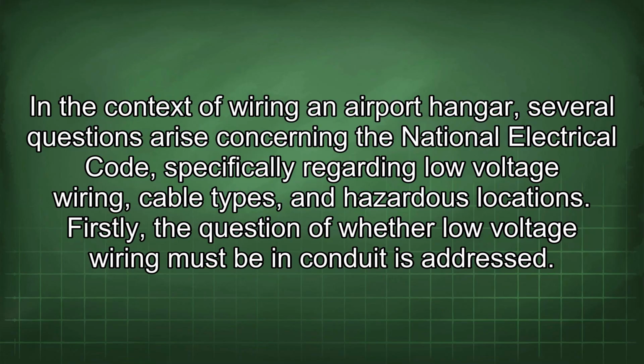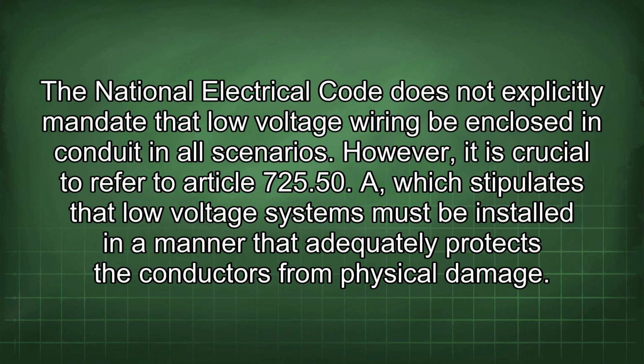In the context of wiring an airport hangar, several questions arise concerning the National Electrical Code, specifically regarding low-voltage wiring, cable types, and hazardous locations. Firstly, the question of whether low-voltage wiring must be in conduit is addressed. The National Electrical Code does not explicitly mandate that low-voltage wiring be enclosed in conduit in all scenarios.